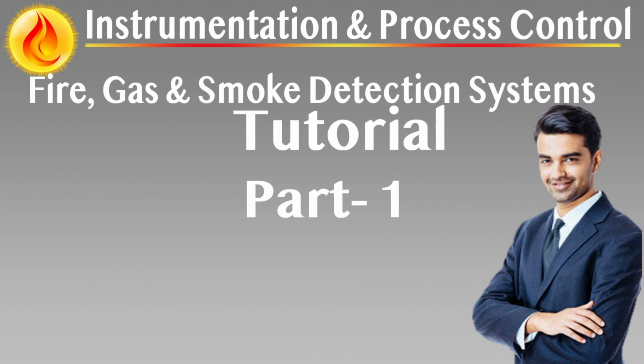A reliable fire, gas, and smoke (FGS) detection system begins with purposeful sensor selection, anchored in hazard severity, environmental demands, and integration performance. Detector technologies must be tailored not only to detect hazards early, but also to avoid spurious alarms and withstand operational stressors such as weather exposure, high temperatures, and mechanical vibration. Selection is not about device preference, but functional alignment with system resilience, fault tolerance, and diagnostic transparency.